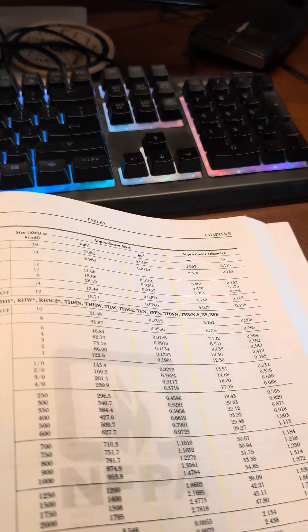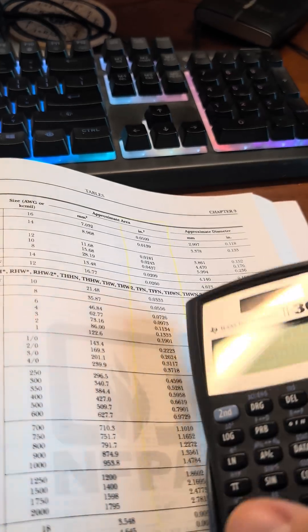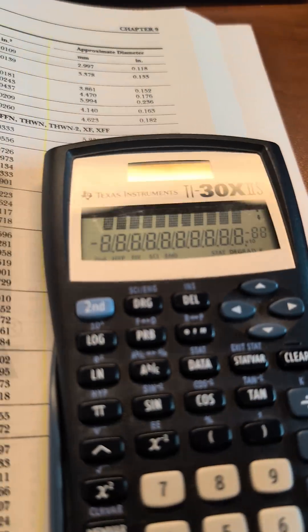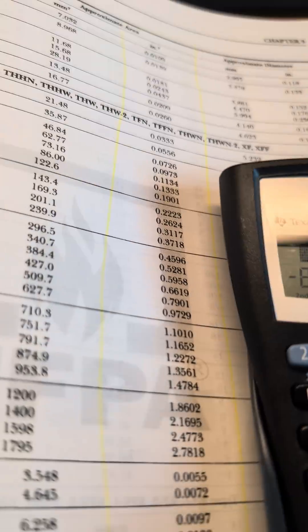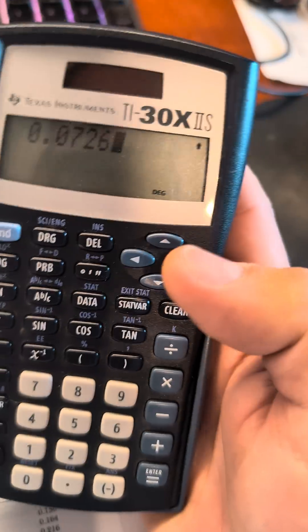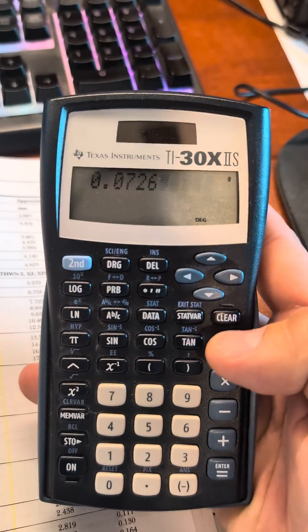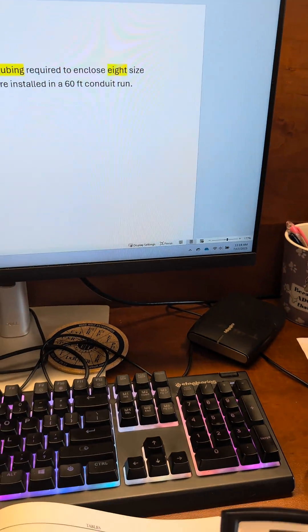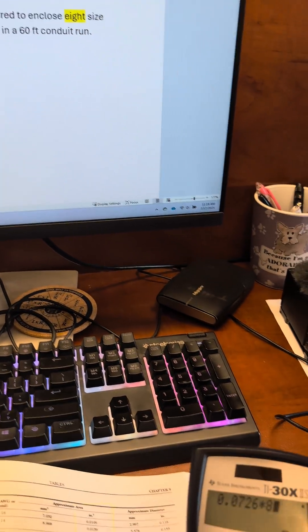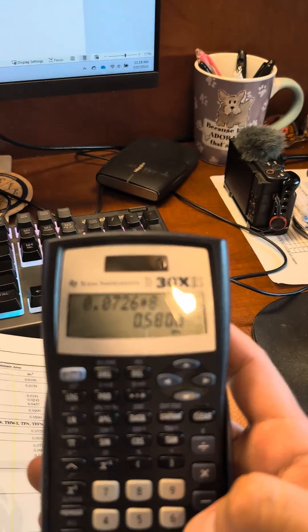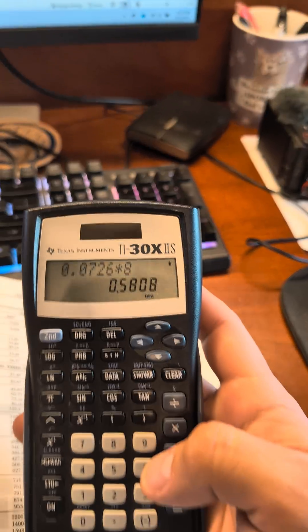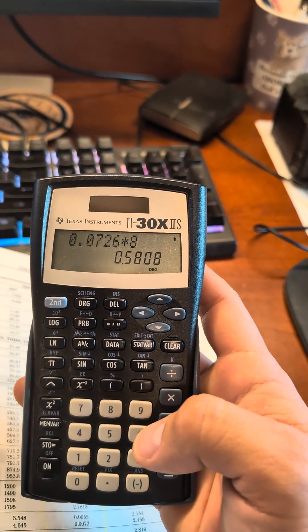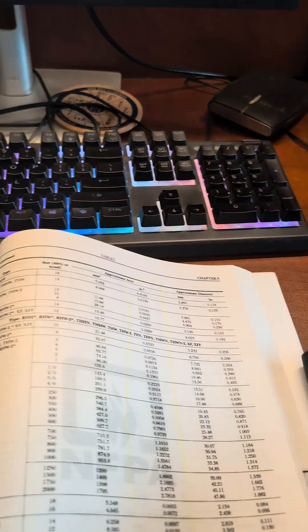So how we do this is we take our calculator: 0.0726, and then we have 8 wires times 8. That means we have to have a total volume of 0.5808 square inches.